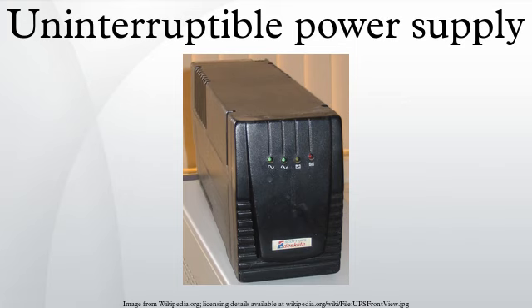Difficulties faced with generator use. Power factor. A problem in the combination of a double conversion UPS and a generator is the voltage distortion created by the UPS. The input of a double conversion UPS is essentially a big rectifier. The current drawn by the UPS is non-sinusoidal. This can cause the voltage from the AC mains or a generator to also become non-sinusoidal. The voltage distortion then can cause problems in all electrical equipment connected to that power source, including the UPS itself.